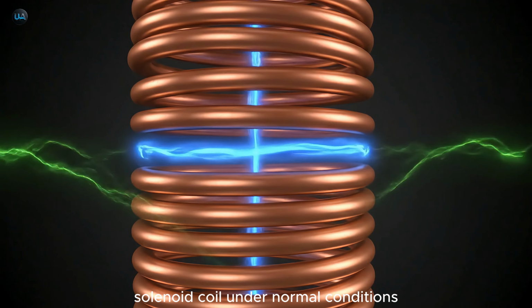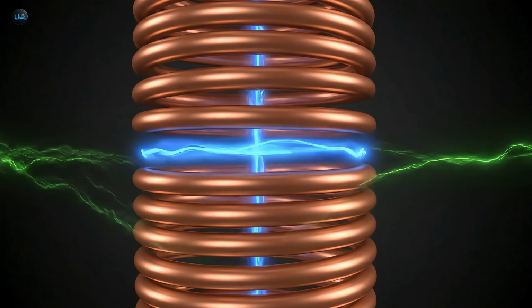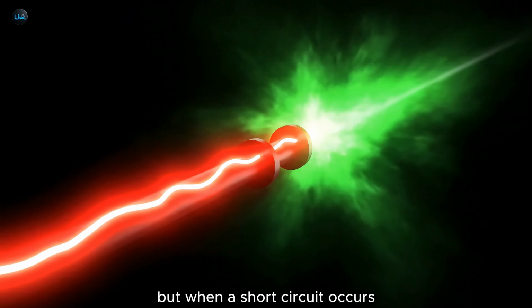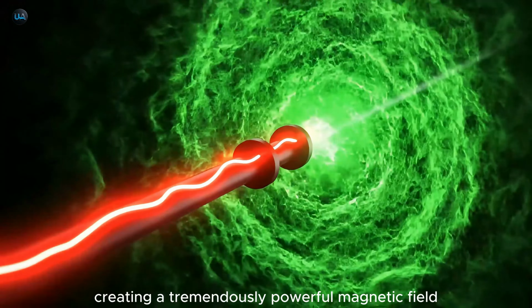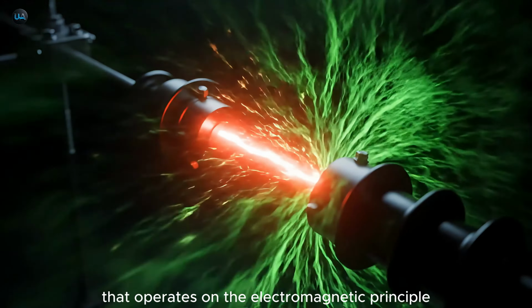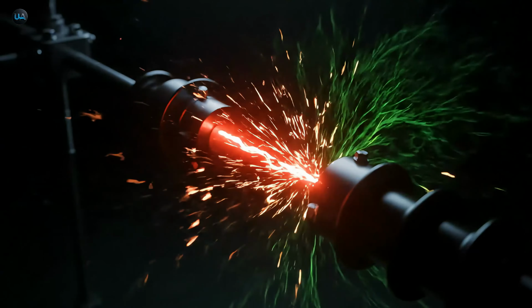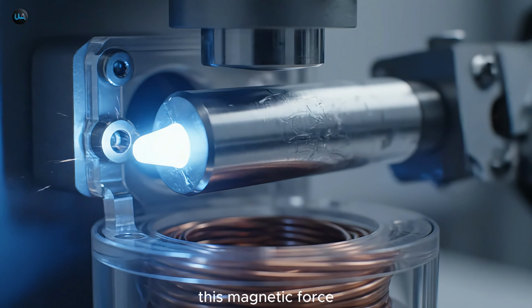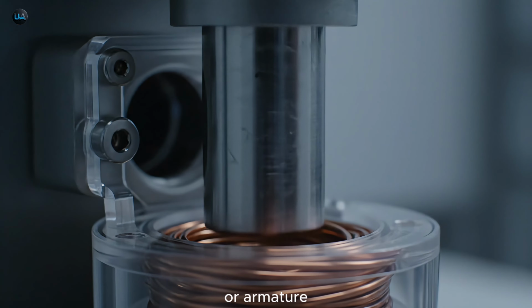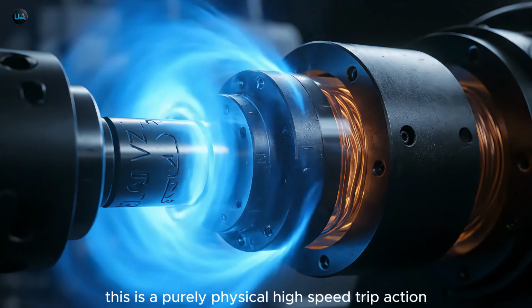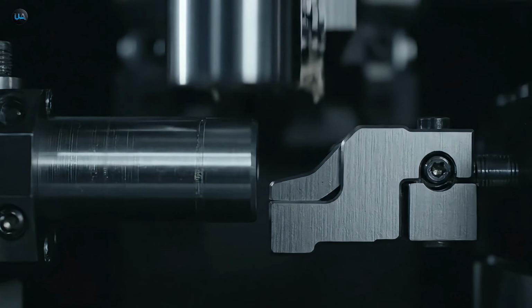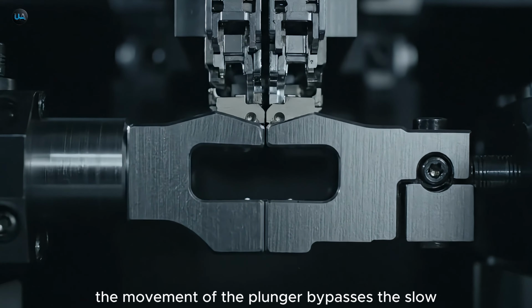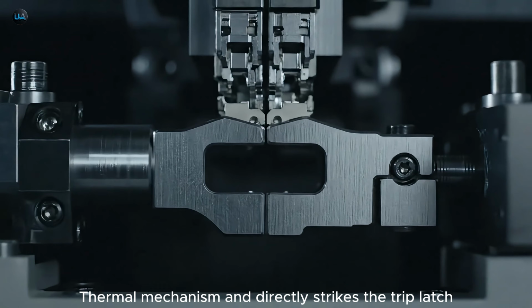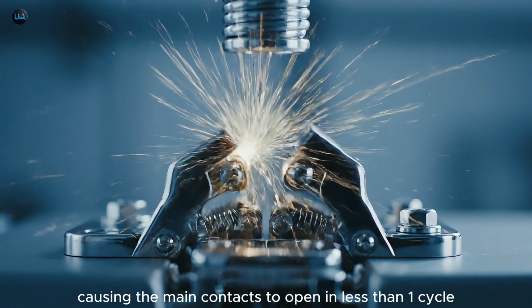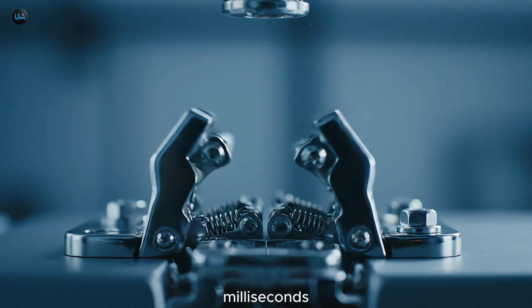The current passes directly through a tightly wound solenoid coil. Under normal conditions, the magnetic field is negligible. But when a short circuit occurs, the current instantly jumps, creating a tremendously powerful magnetic field that operates on the electromagnetic principle. This magnetic force instantly pulls on an adjacent magnetic plunger or armature. This is a purely physical, high-speed trip action. The movement of the plunger bypasses the slow thermal mechanism and directly strikes the trip latch, causing the main contacts to open in less than one cycle, in milliseconds.